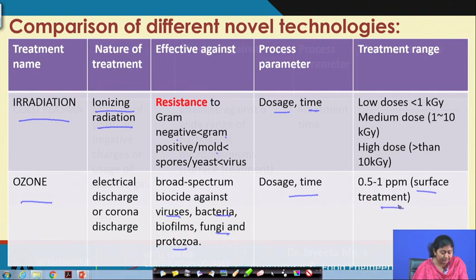Ozone: the nature of treatment is electrical discharge or the corona discharge method. Ozone is a triatomic gas that we develop by the corona discharge method, by passing oxygen through a high voltage electrical discharge. Ozone is a broad spectrum biocide against viruses, bacteria, fungi, protozoa, etc. It acts on both spoilage and disease causing organisms. Here also the dose and time can be changed, and 0.5 to 1 ppm is required for the surface treatment.